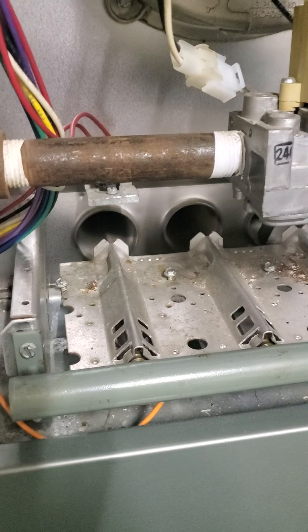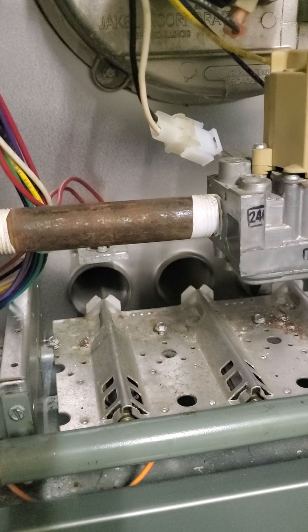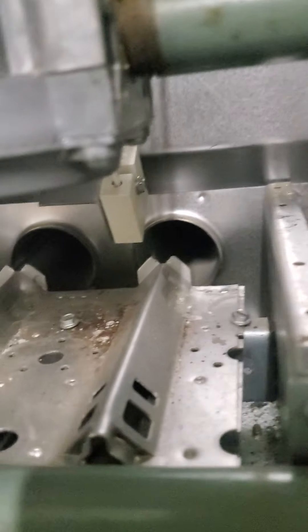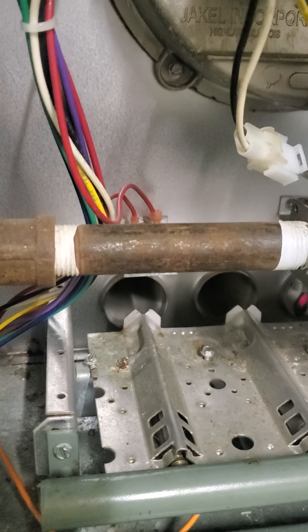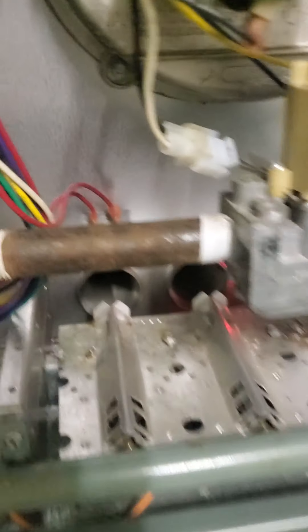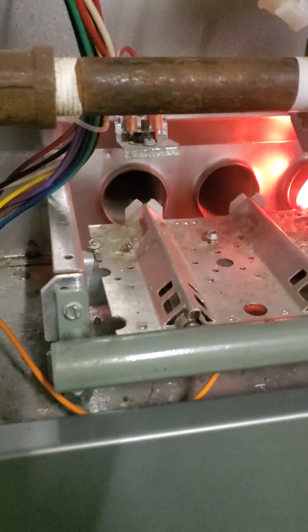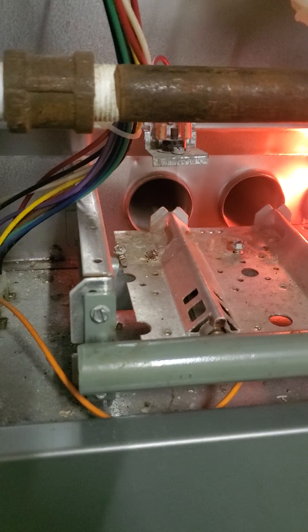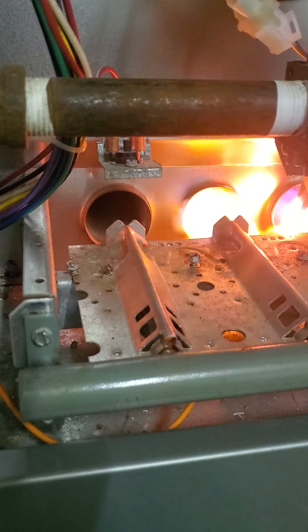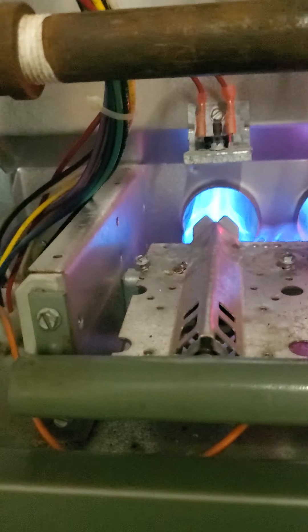Please let that be it. So my fan's turning on. Let's see if the igniter works now. Oh, it's burning — I think it's gonna turn on. Oh, there's the click! We have heat! That's amazing — look at it!